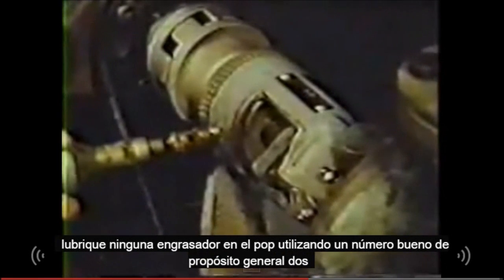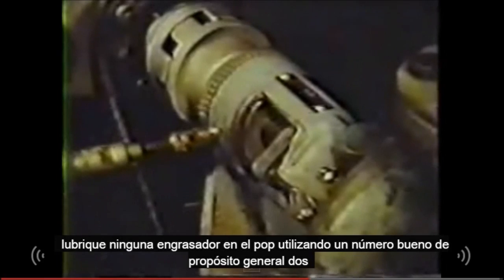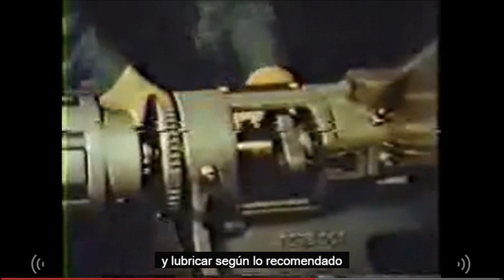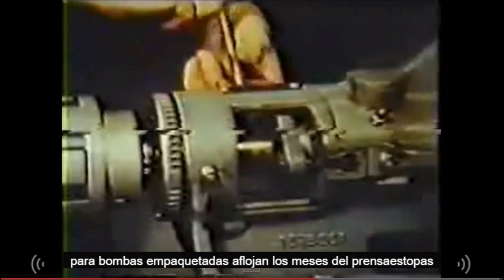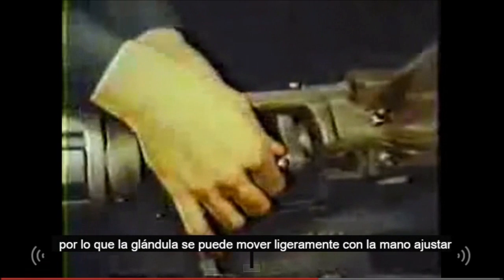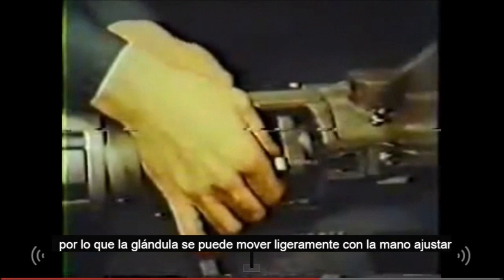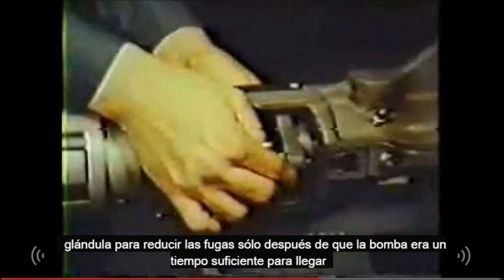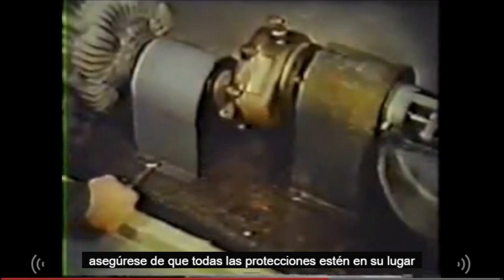Lubricate any grease fitting on the pump using a good general-purpose number 2 ball bearing grease. Check any gear reducer or motor coupling and lubricate as recommended. For packed pumps, loosen the packing gland nuts so the gland can be moved slightly by hand. Adjust the gland to reduce leakage only after the pump has run long enough to reach constant temperature. The packing should weep a little to keep it cool and lubricated. Make sure all guards are in place.